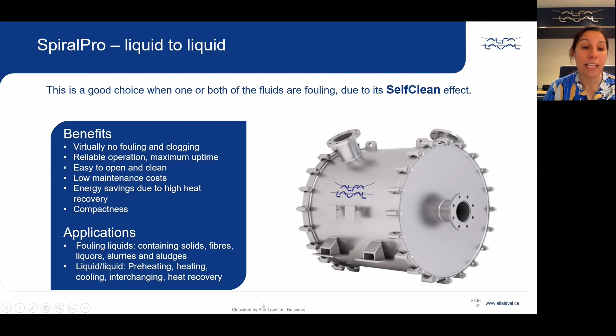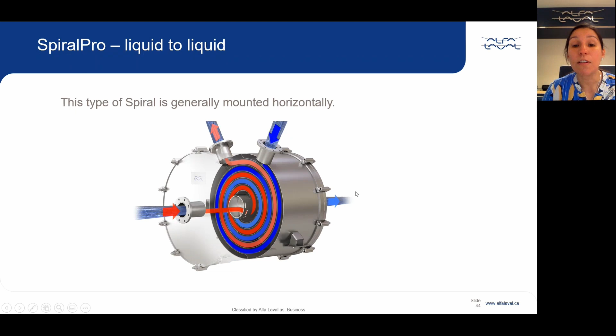Typically mounted horizontally, this is how the spiral would look. We have the hot inlet at the center of the spiral, then moving through the heat exchanger around the center, and the outlet of the hot side on the shell side, or the periphery of the spiral, and the cold fluid moving in the opposite direction.